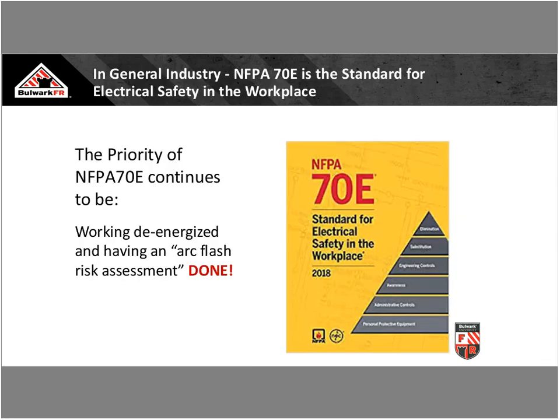On our low voltage side, general industry inside our buildings, away from the power generation, transmission, distribution, and metering, inside the building now, NFPA 70E. NFPA 70E primarily was written to make sure that you do an arc flash risk assessment of your facilities. What does that risk assessment generate at the end of it? It generates a little sticker. That sticker says the incident energy or the category of protection needed working on this piece of equipment, if it fails, is X. We basically tell electrical workers how big a bomb they're standing in front of so that they can dress accordingly.